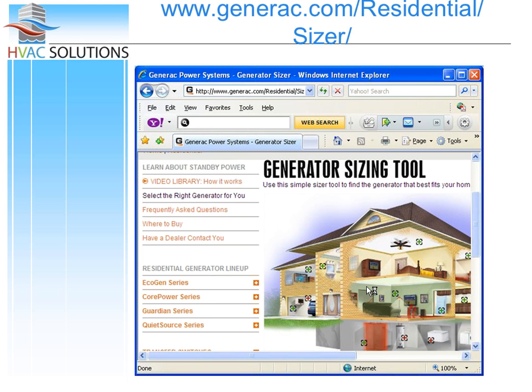I put this sizing guide up here because sometimes homeowners will say, well, I talked to Generac and they said I only need an 8 kW generator. I say, well, this sizing tool is more for homeowners asking how many refrigerators do you have, do you have ceiling fans, do you have this, do you have that. And you're going to go there and say, well, you really need a 15 kW because you have a 4-ton air conditioner. Just know that it's out there and people will tell you Generac said so, and it's not always the case.